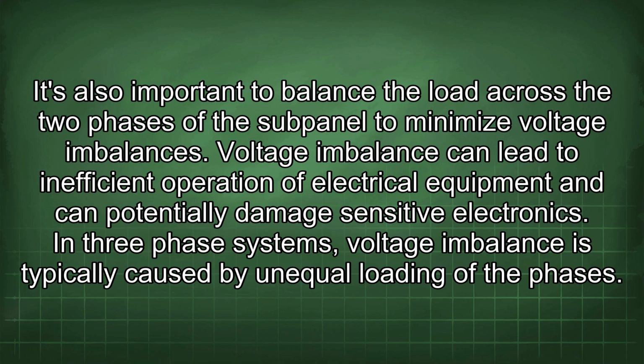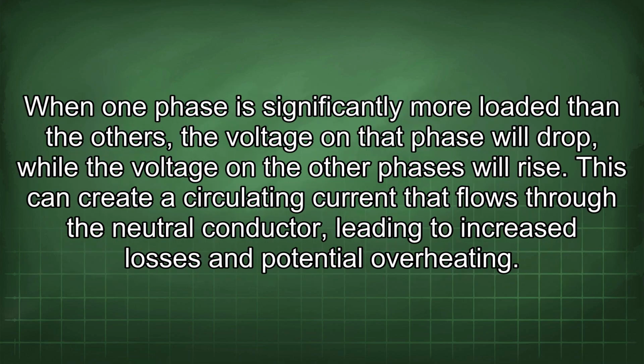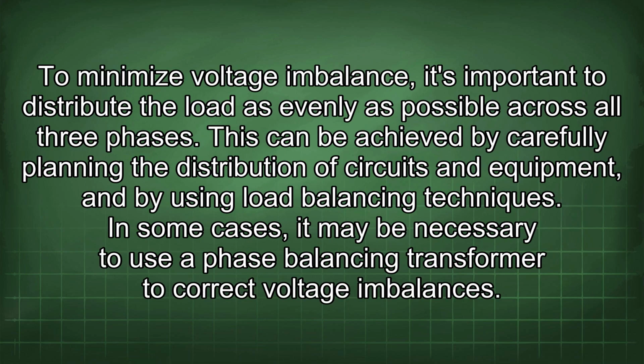In three-phase systems, voltage imbalance is typically caused by unequal loading of the phases. When one phase is significantly more loaded than the others, the voltage on that phase will drop, while the voltage on the other phases will rise. This can create a circulating current that flows through the neutral conductor, leading to increased losses and potential overheating. To minimize voltage imbalance, it's important to distribute the load as evenly as possible across all three phases. This can be achieved by carefully planning the distribution of circuits and equipment, and by using load balancing techniques.